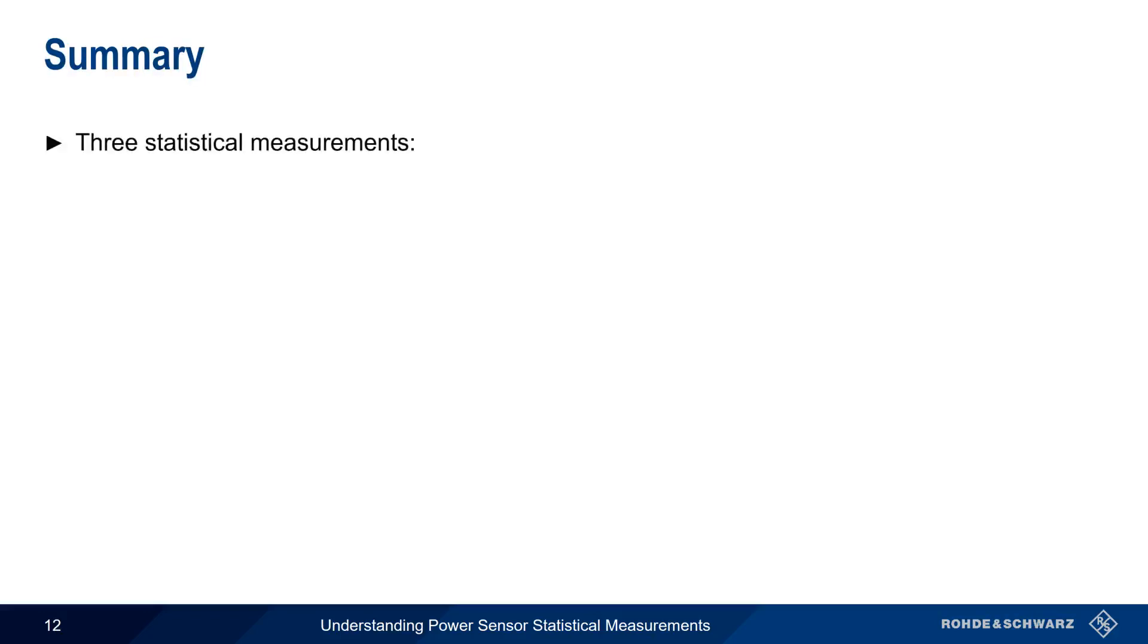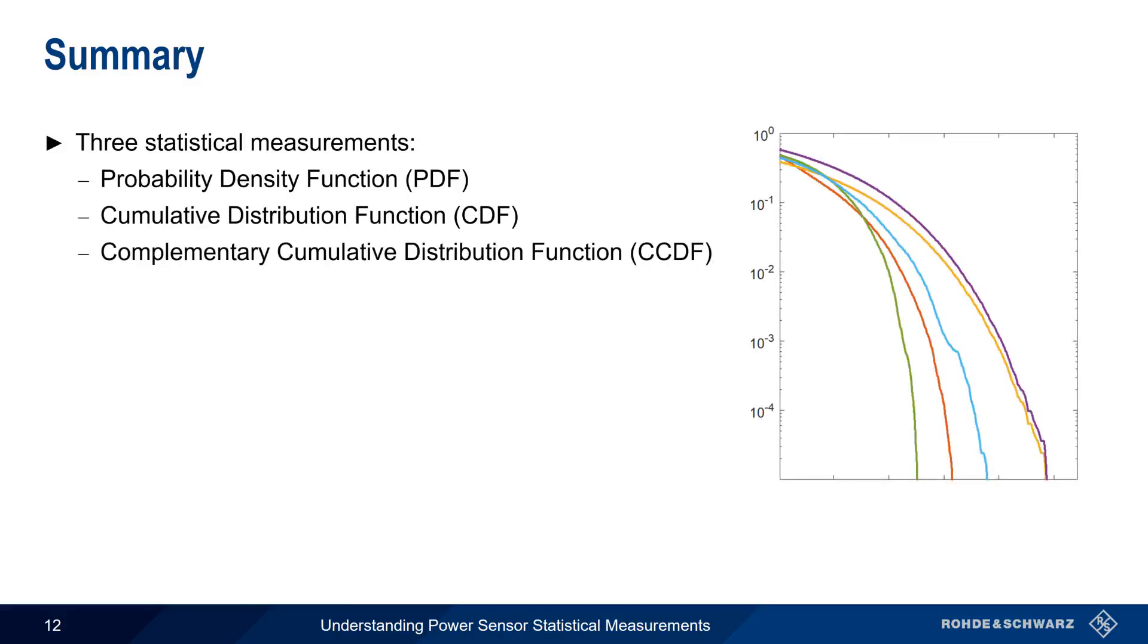So in summary, there are three statistical measurements we can make with power sensors. The probability density function, or PDF. The cumulative distribution function, or CDF. And the complementary cumulative distribution function, or CCDF. Of these, CCDF is by far the most common and the most important.